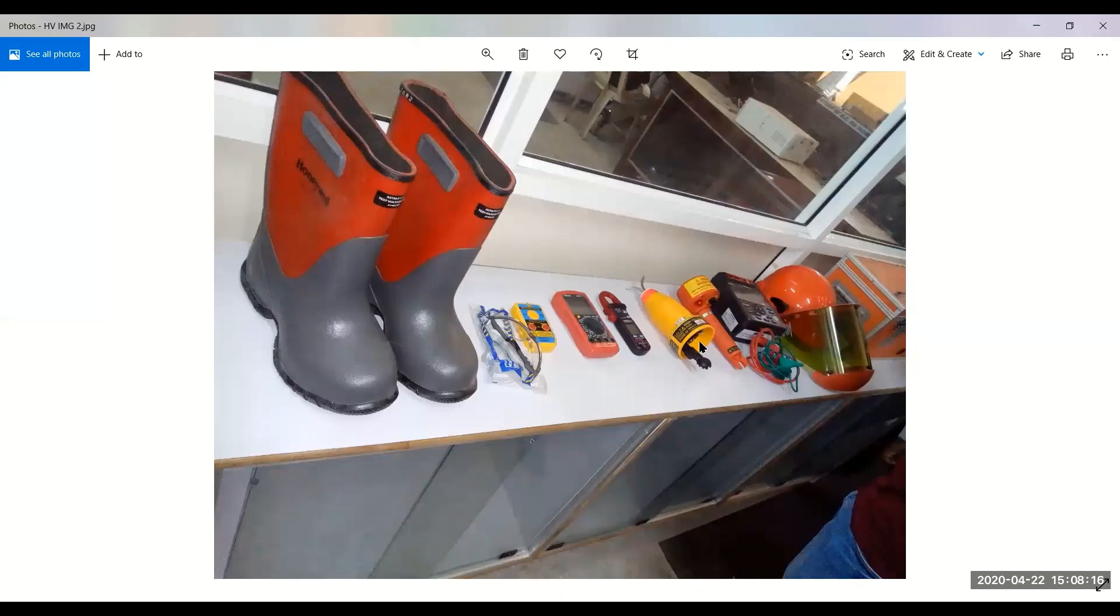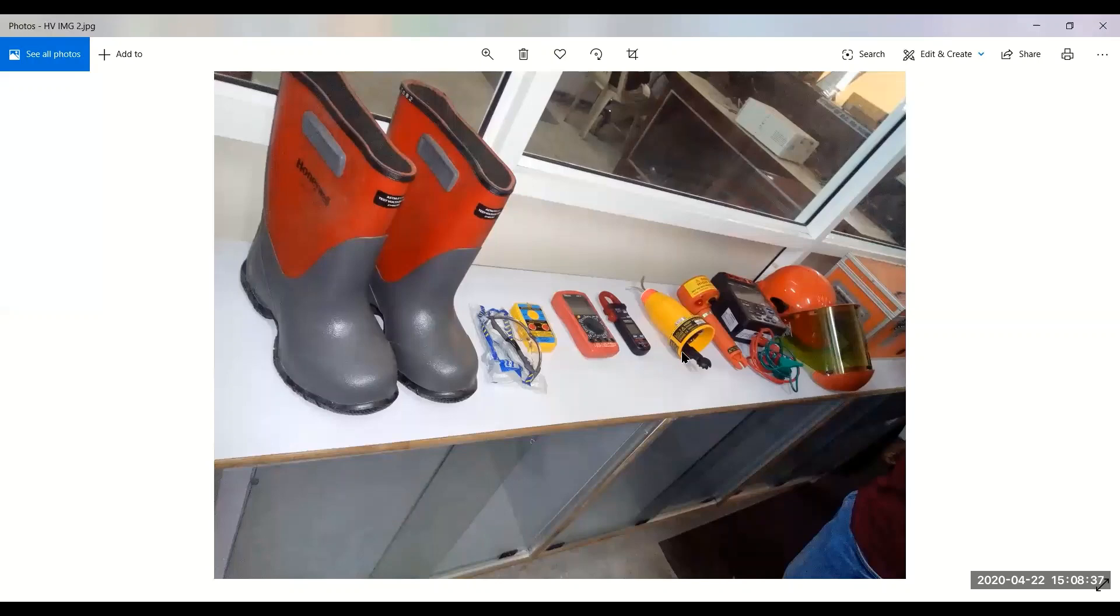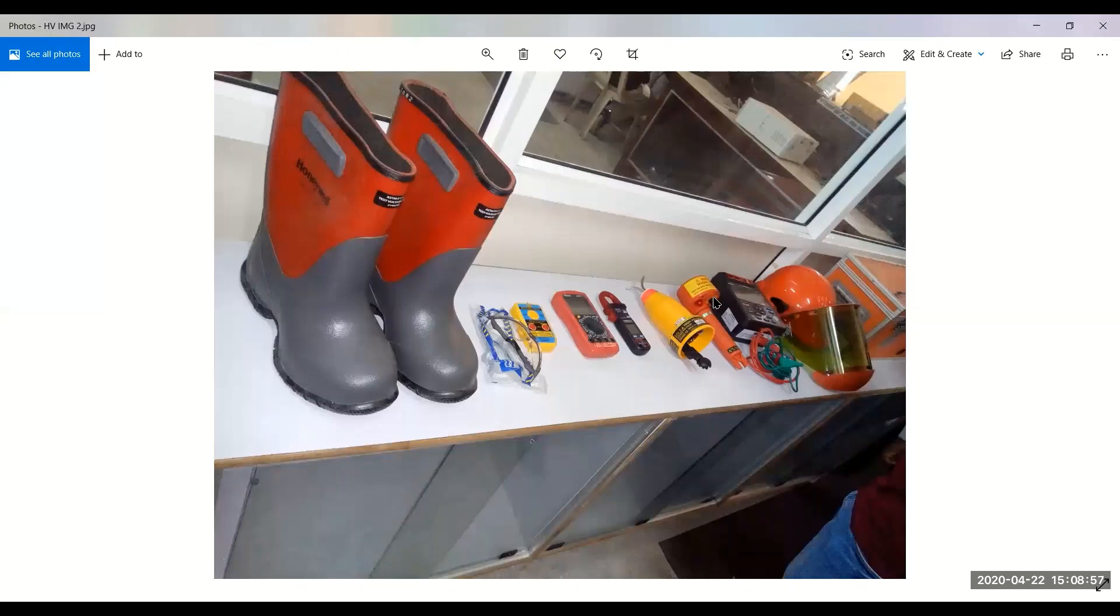There is a setting inside. It is on. Then you have a setting. There is a power lamp, red lamp. When you are touching this, the red lamp will glow and it will give alarm. You can check the LED power lamp. This is the low, and it is in 220 volt, 440 volt, 1,000 volt, 2,000 volt, 2.9 kV, then you're having 6.6 kV, 11 kV, and up to 11 kV.